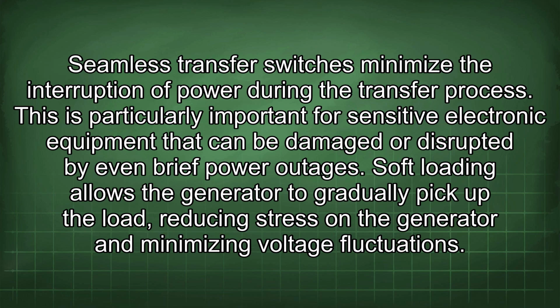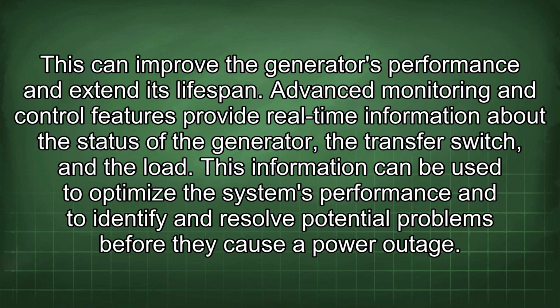This is particularly important for sensitive electronic equipment that can be damaged or disrupted by even brief power outages. Soft loading allows the generator to gradually pick up the load, reducing stress on the generator and minimizing voltage fluctuations. This can improve the generator's performance and extend its lifespan.